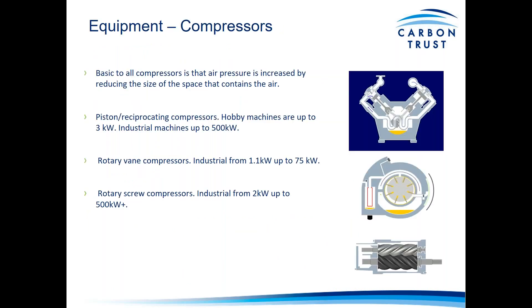Looking at the main component — the compressors. All a compressor does is pressurize the air. The main types, for the smaller ones — although they can range up to half a megawatt — would be the piston and reciprocating compressors, which you'd often hear in garage workshops. There's also the rotary vane, typically for industrial use from one up to 75 kilowatts. And then you've got your rotary compressors, which would typically be going up to the larger machines.